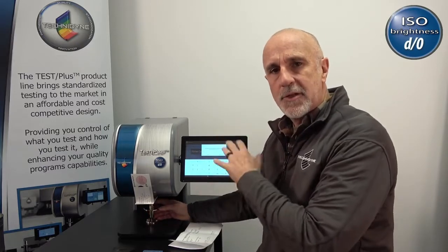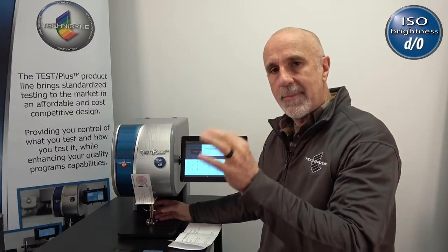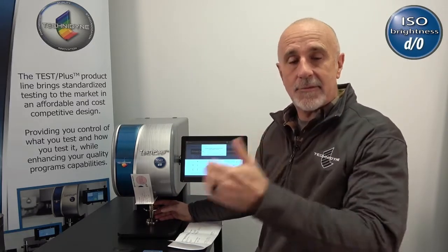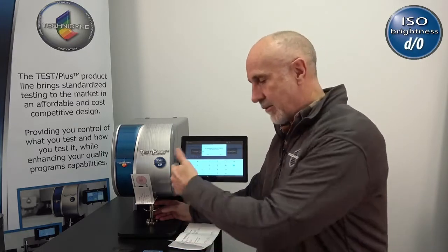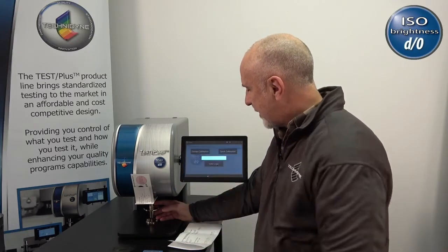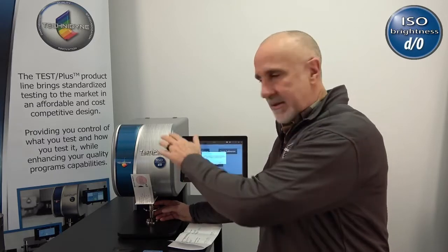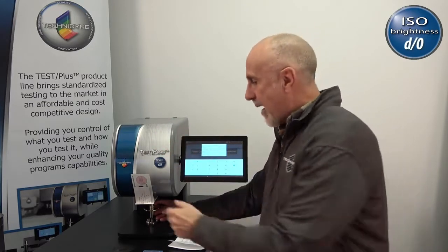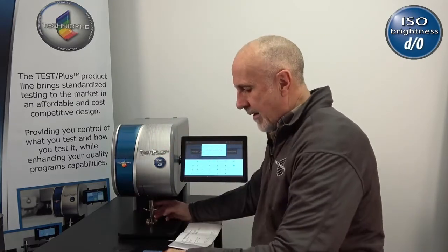So 90.9 is here. That was already there in this particular case because I'd already used these standards once to go through a calibration sequence, and the software always maintains the last value that you had put into it. Okay, so the 90.9 is there, then I hit calibrate, and now we're forcing this instrument to agree with the master. I pull the standard out.